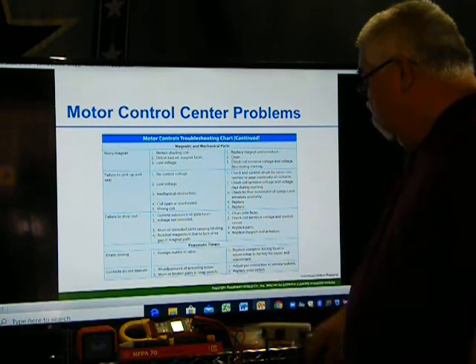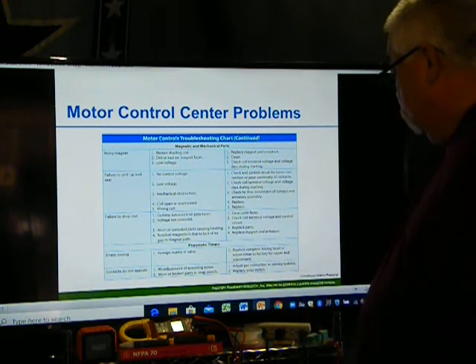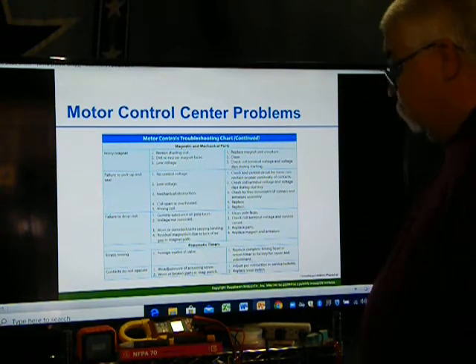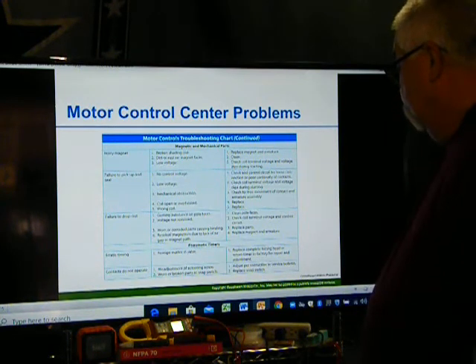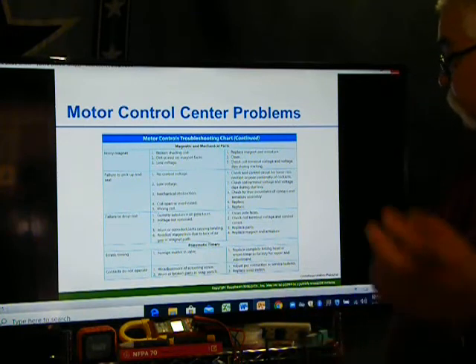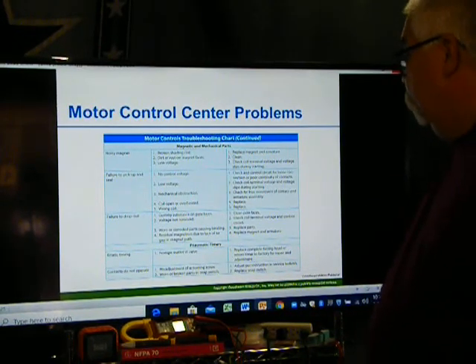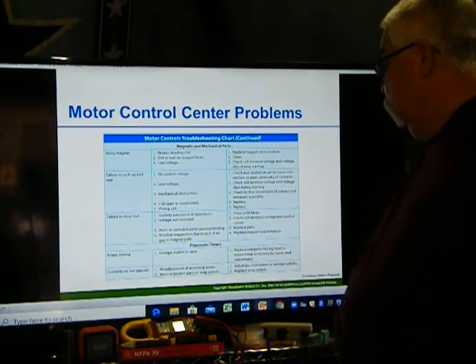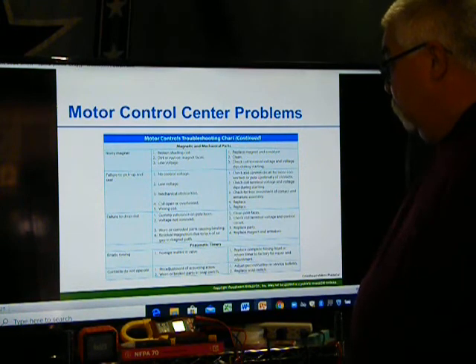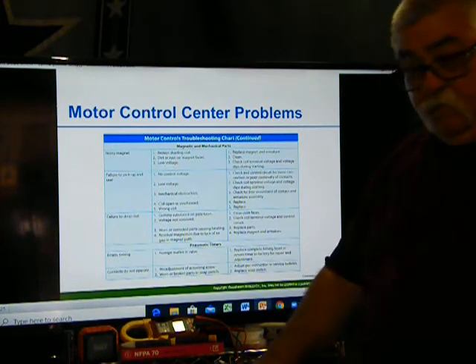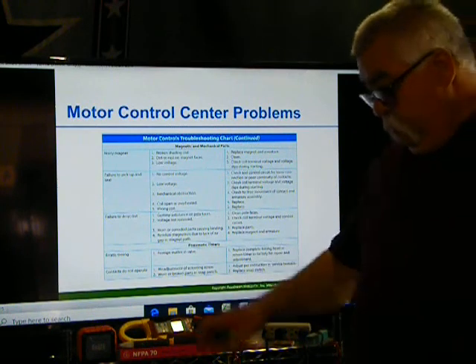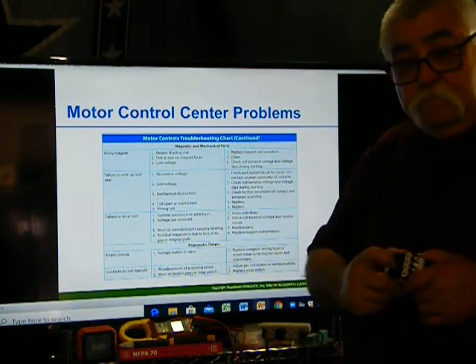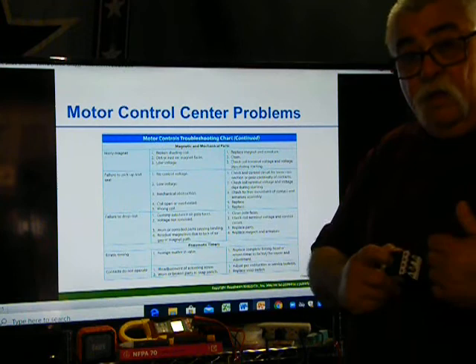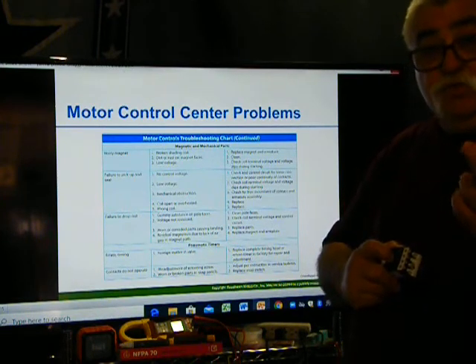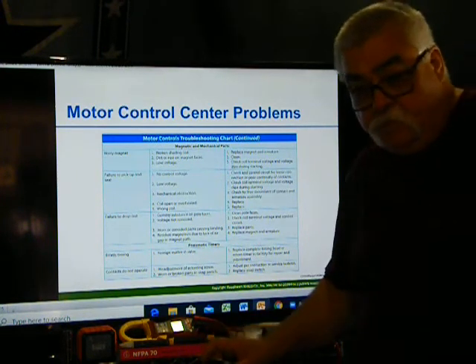This is for pneumatic timers. Adjust per instruction service bulletin, replace the snap switch, so your switch may be broken. Replace the complete timing head or return the timer to the factory for repair and adjustment. So it's foreign matter. Failure to drop out: gummy substance on pole surfaces, clean pole surfaces. Voltage not removed. So again, you go in there and you hit the stop button and the contactor stays on. Well, somewhere along the line something is faulty. So the switch may be stuck, so you have your push buttons.